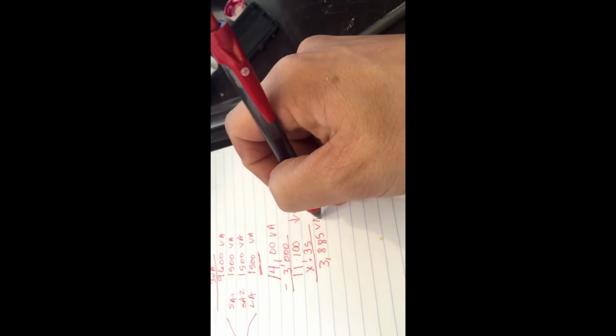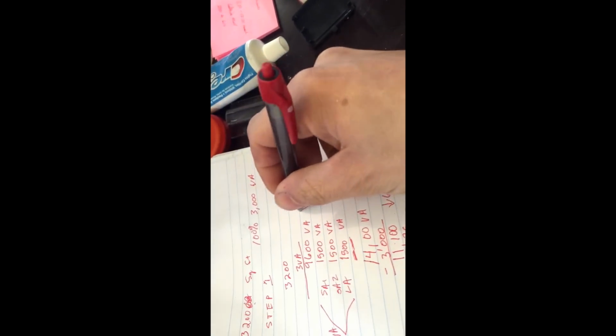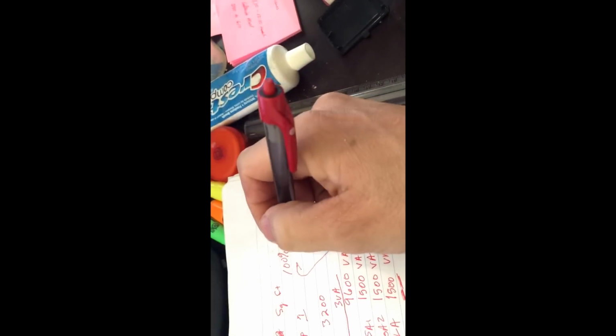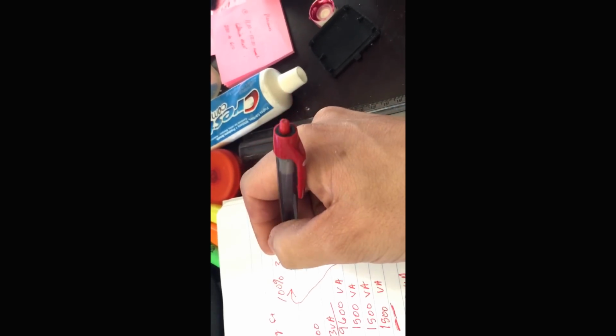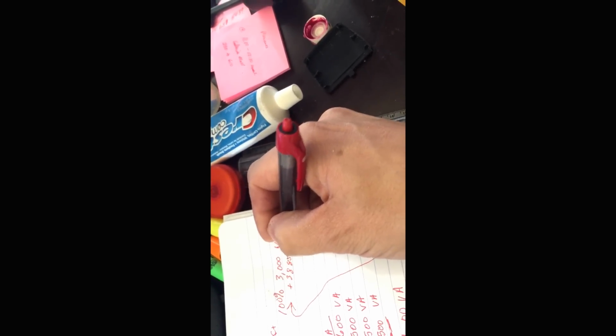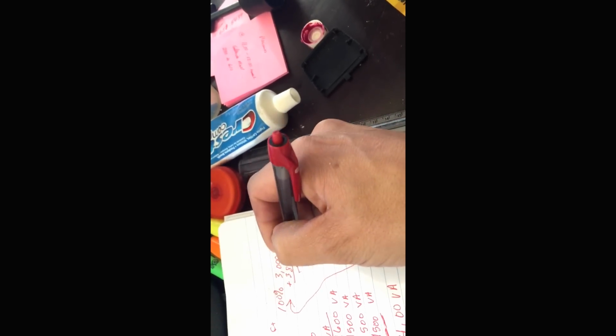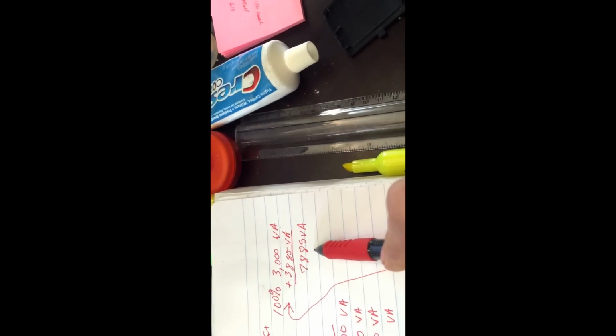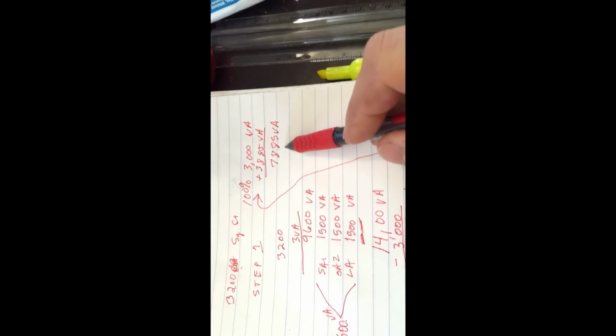That's the amount that we can take this derating of 35% against. So we take the 11,100 and multiply that times 0.35. That gives us 3,885. This number, 3,885, in volt amps of course, is the balance that we bring up here and include with the number that was saved at 100% of the first 3,000. So plus 3,885 VA gives us a total of 7,885 volt amps. And that, gentlemen, is the minimum required demand load for a single family residential dwelling in the 2014 code book. That's the minimum amount we have to have.